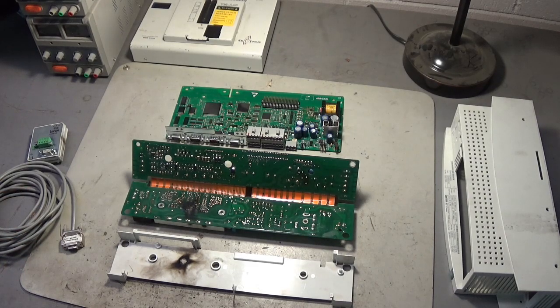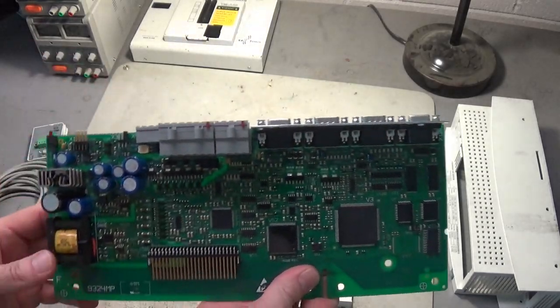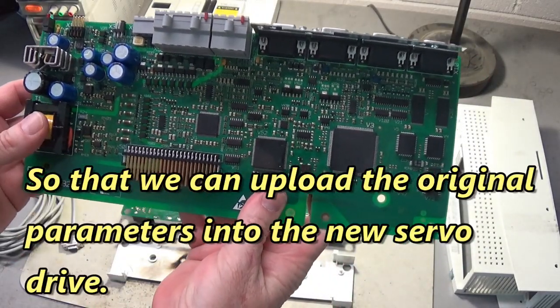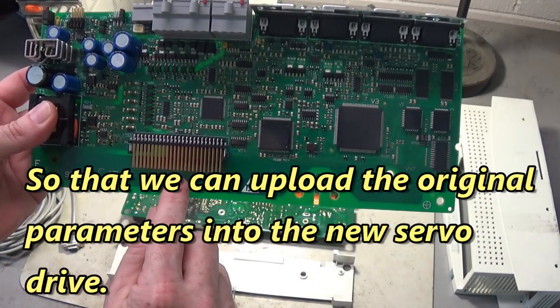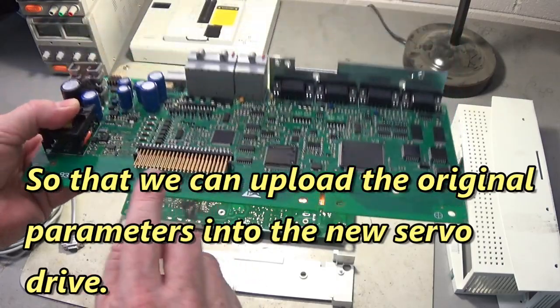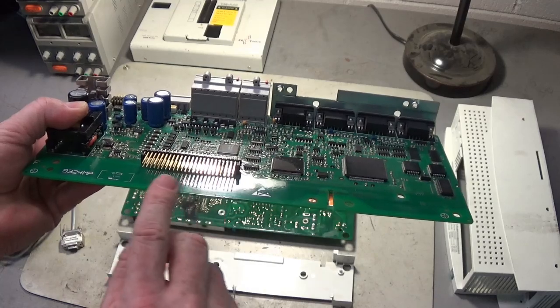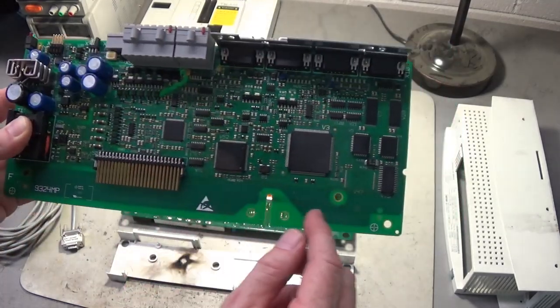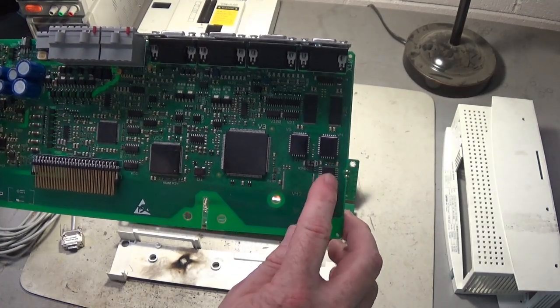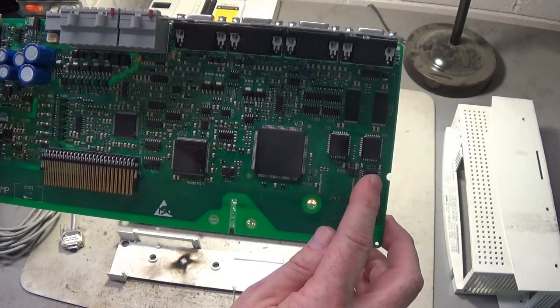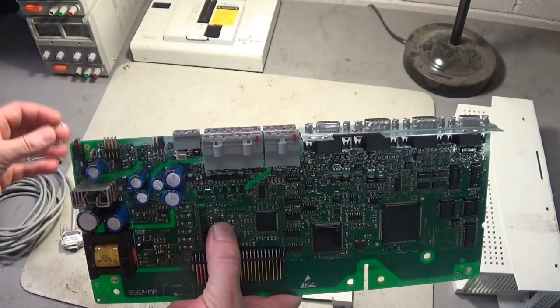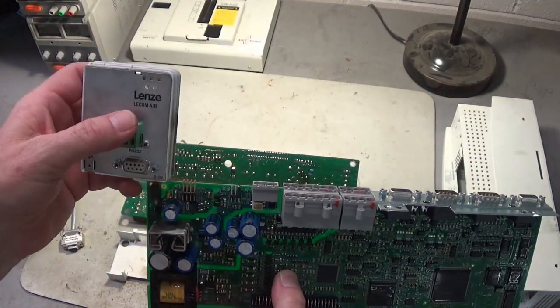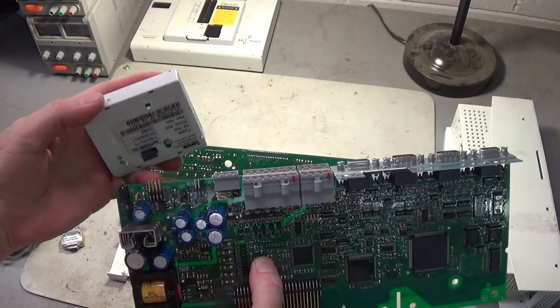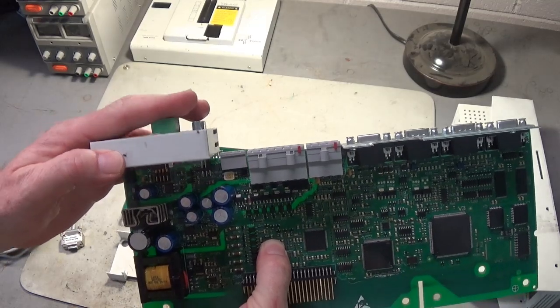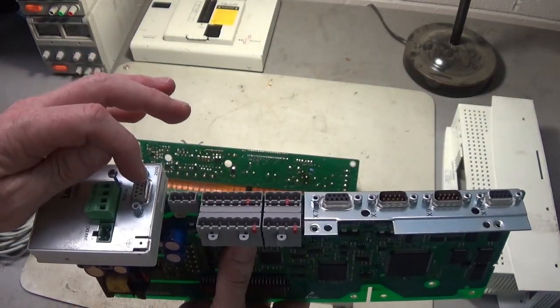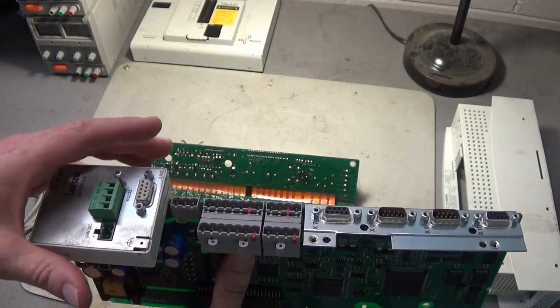What we need to do here is we need to get the parameters off of the control board of this blown up drive. So we're going to put 5 volts and 24 volts into this stake connector right here. At the end of the video, I'll show you what pins I connect to, and as we go along, I'll show you. But the parameters are held in memory over here in this flash, and we're going to connect this LECOM to the Lenze COM port right here. After we power up this drive, we'll be able to connect our laptop to this RS-232 port.